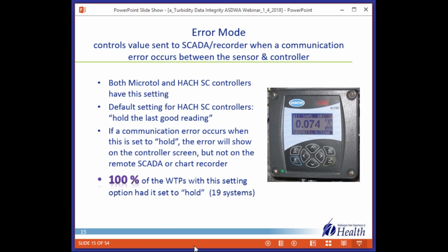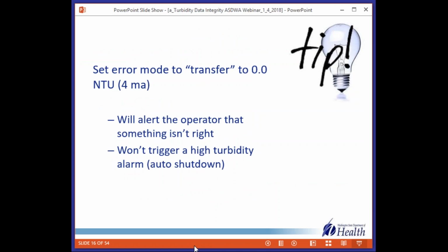100% of the treatment plants with the setting option had it set to hold. There's 19 systems. So we think that a better option or better mode is to set it to transfer, and we want this transfer mode, which value you're going to send it to let the operator know that something is wrong, but we don't want some unintended consequence, like an auto shutdown because you send it to a high alarm, or equally as bad, you trigger a regulatory violation. Because remember, the issue here is that the turbidimeter is no longer communicating with the controller. It's not necessarily that the turbidity itself is wrong.